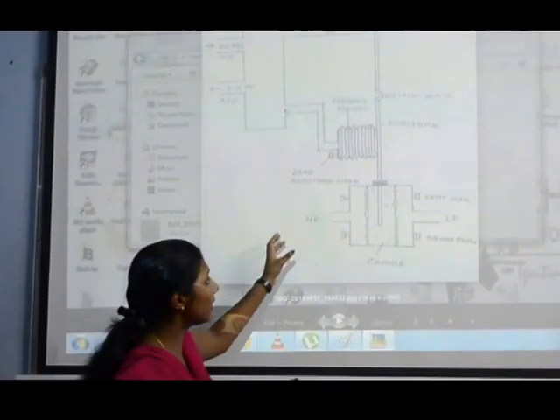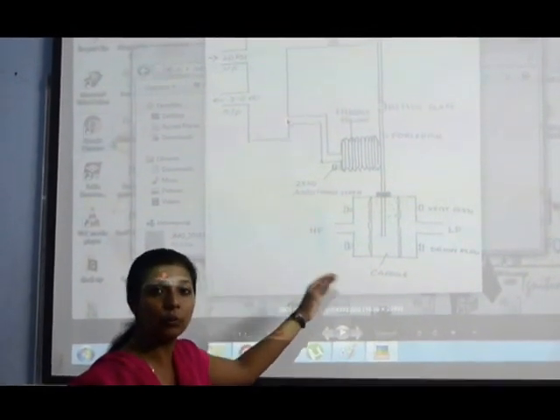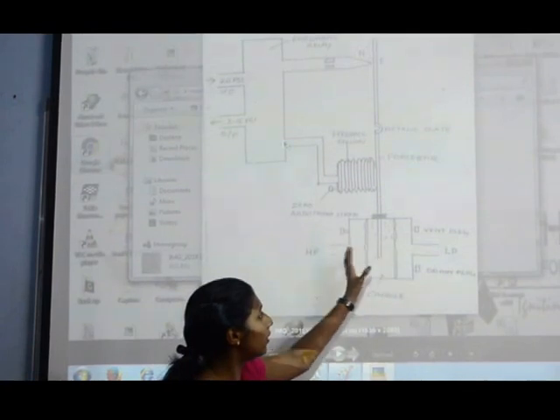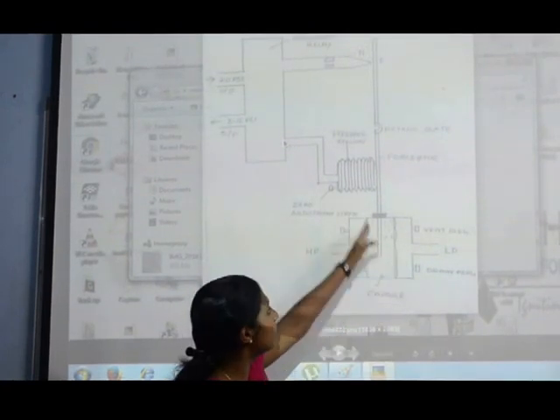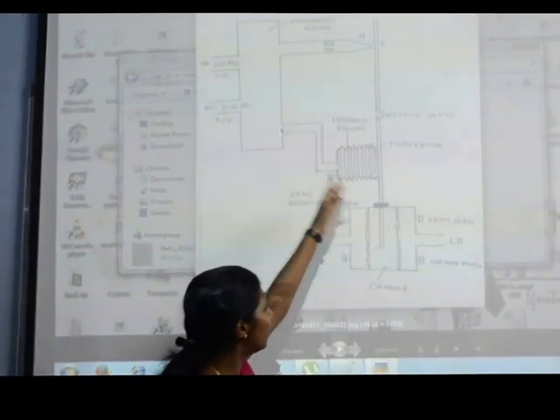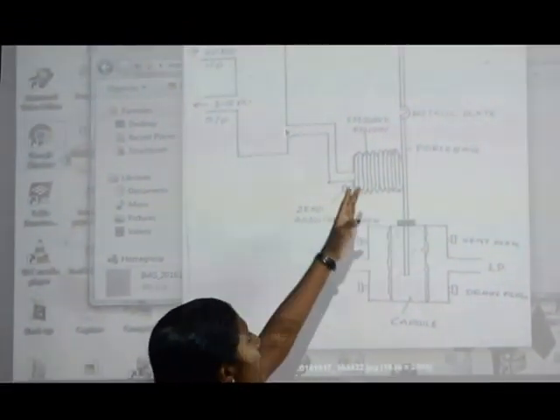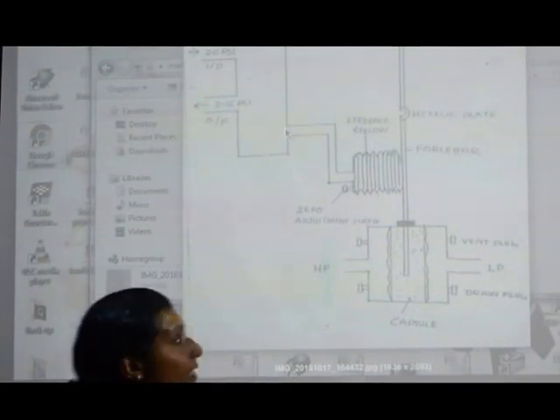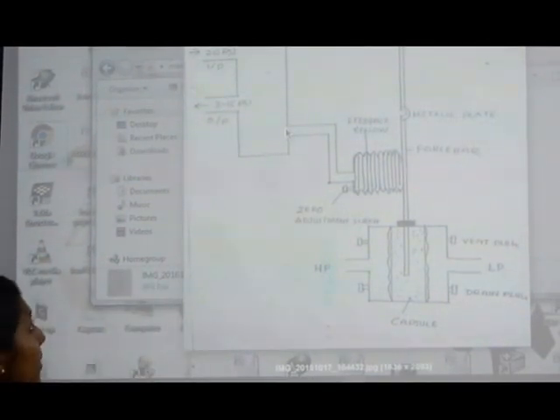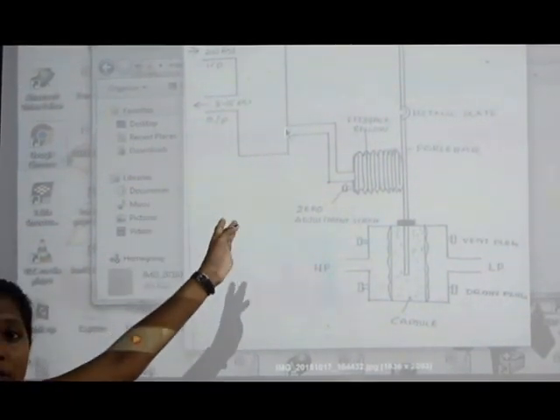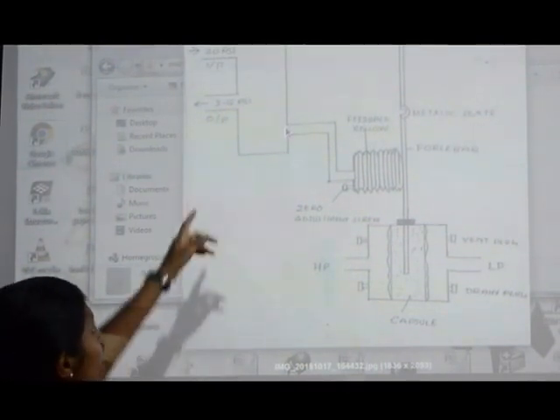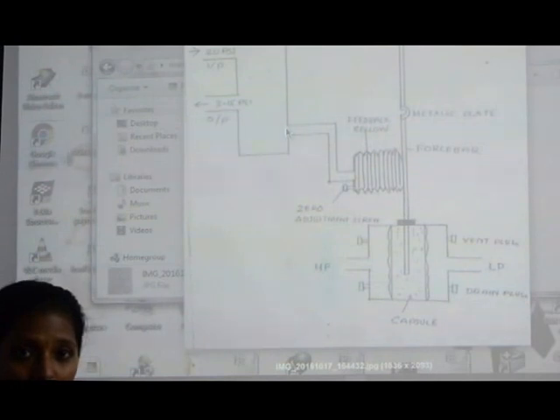If we are giving the 100% output or the maximum output, this capsule will be extended to this side and will directly act on the force bar. That flapper will be coming near to the nozzle side, and that means the leakage on the flapper nozzle side will be very much reduced. We are able to get a 15 psi output.